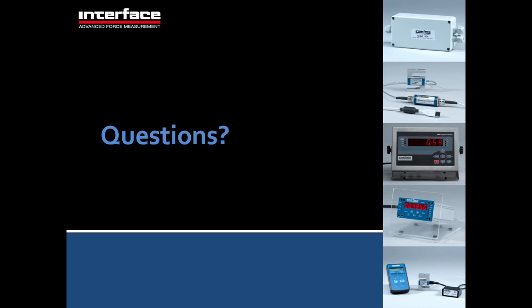So there's a variety of reasons why people may not do it, but they definitely can benefit from calibration, especially the ones that actually have millivolt per volt measurement capability. And in our case, it would be the 9860, the 9040, 9320. Those are three that come to mind. Another thing we have is a millivolt per volt transfer standard, which is a very nice, handy device that's used for calibrating instruments in the field. Basically it has a dial on it that can be set to precisely output a certain millivolt per volt value. So for example, you might set the simulator to 3.0000 millivolts per volt, and then you can use that to scale the instrument in the field, or you can actually use that to calibrate the internal millivolt per volt values of the instrument. So a number of ways to calibrate these things. Coming back to the factory is certainly one of them. It can also be done in the field using a simulator or with applied loads or various other methods.